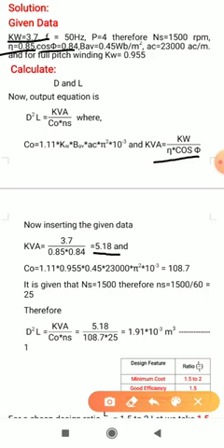And similarly, if you calculate the CO by using this expression, the CO is equals to 1.11 into 0.955, which is the kW, into 0.45 is the BAV, into 23,000 it is AC, pi square into 10 to the power minus 3, and if you calculate this you will get 108.7. And again in this expression of the D square L, we require the NS also, which is the synchronous speed in RPS. But it is given here in the example NS is equals to 1500 RPM. So we need to convert into the RPS.